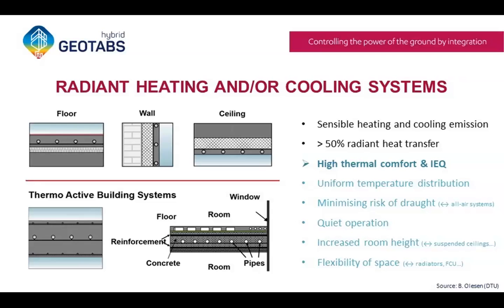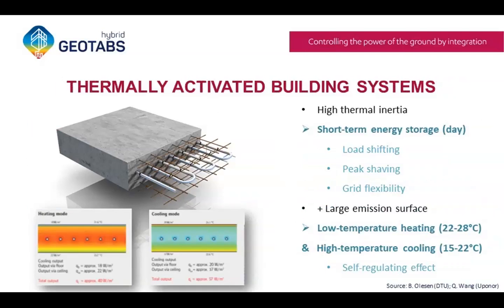In this sort of system, the tubes that distribute heat to the rooms are embedded within the floors, walls, or ceilings. Specifically for thermally activated building systems, they are embedded in the core of the concrete floors, as shown in the example. When we supply heat or cold through the tubes, the entire core, or the entire thermal mass, of this floor can be activated, becoming warmer or colder.